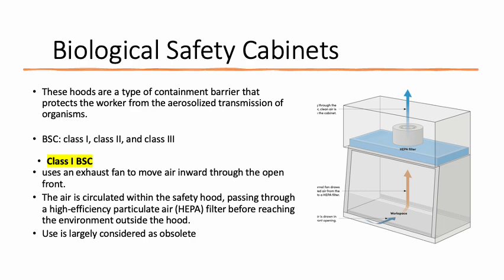Now, tandaan nyo po, your biosafety or biological safety cabinets, the air po that must be flowing inside should be filtered, okay? Pero depende pa rin po yan sa class ng biosafety cabinet. And the most standardized filter that is used on our biosafety cabinets po is the HEPA filter, your high efficiency particulate air filter. Okay? Now, the air will go in the HEPA filter before reaching the environment outside the hood.